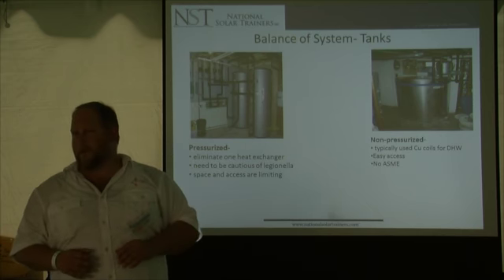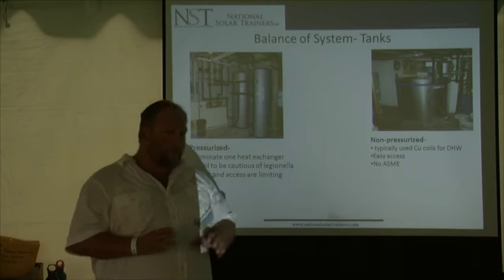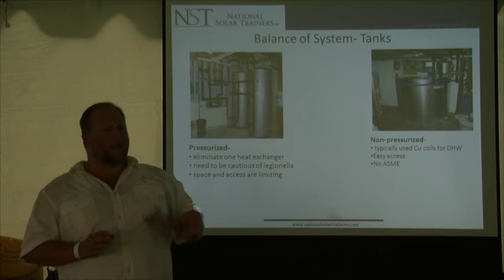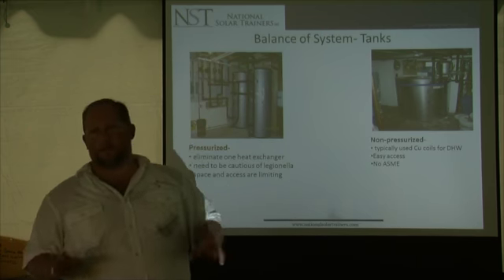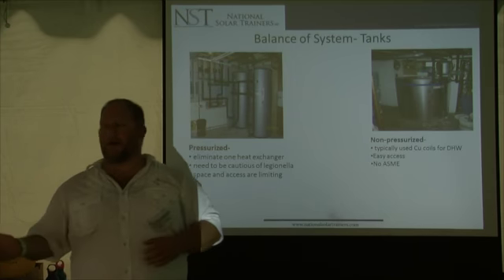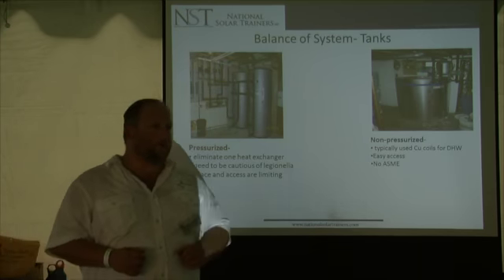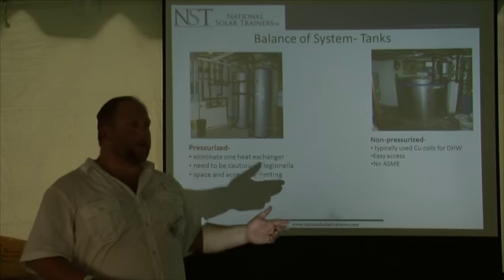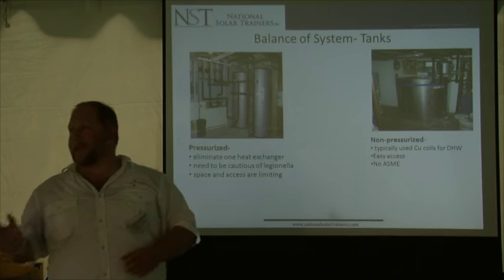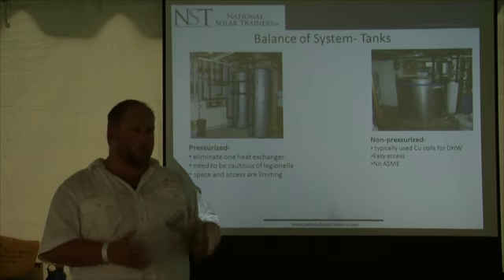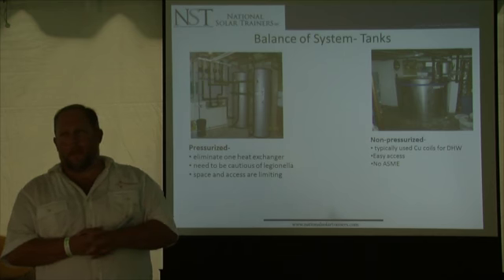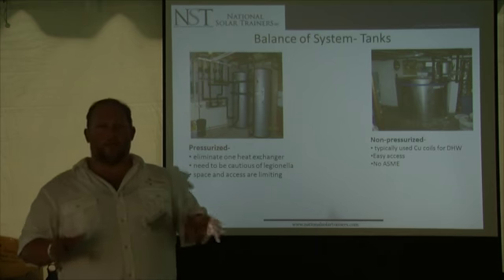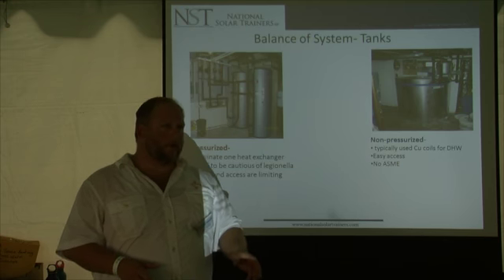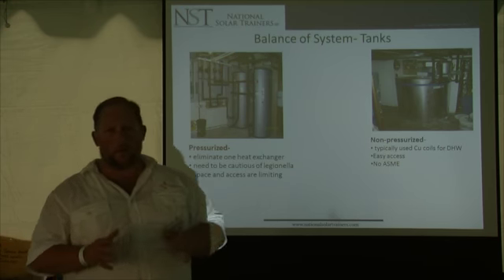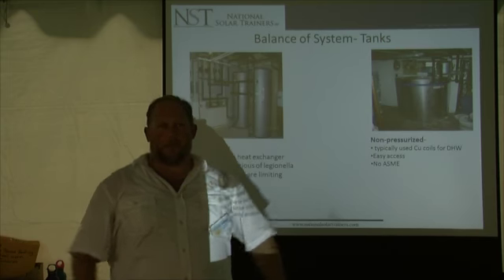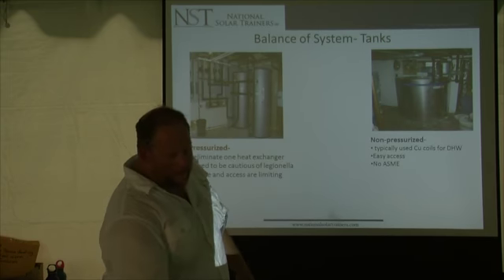Right? So when it comes to a domestic hot water system, it's very simple. It's very straightforward. It's about 2 gallons for every square foot of collector. 2 gallons of storage per square foot of collector, you're good. But when it comes to heating systems, it gets real tricky, right? And in my experience, big storage tanks are overrated for heating systems. So don't let somebody talk you into a big, huge storage tank because it's not going to work out the way you wanted it to.